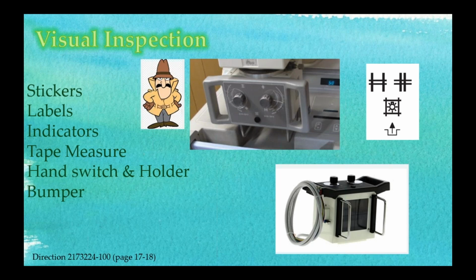So just a little something, I have been on several calls after a physicist comes in and checks the machine and says your field is out of tolerance. It's because the stupid set screws on the knobs have come loose and they're not pointing at the right one. I put it at the right distance, I make my shot, I don't pay attention to where the knobs are, and it's accurate as heck. So all I got to do is loosen the set screws on the knobs and tweak them back to where it looks nice for the physicist to be in the right scale, right?